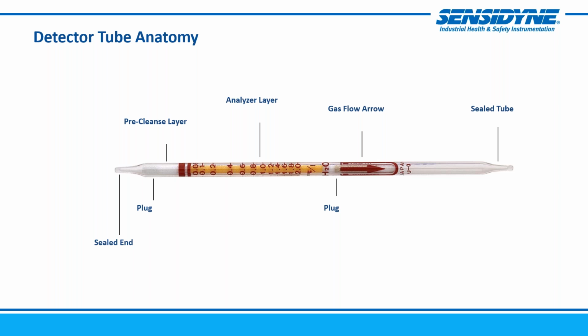So again, in the middle, you see the analyzer layer along with the scale for that range for that particular detector tube. After that, again, there's another plug, and that keeps those materials very tightly aligned in that section. And it's important that it be very tightly aligned, because once that scale is put in place, you don't want materials moving behind it. So it is specially designed so that the material is held in place, and that the reagent change is both accurate and consistent across all the tubes.